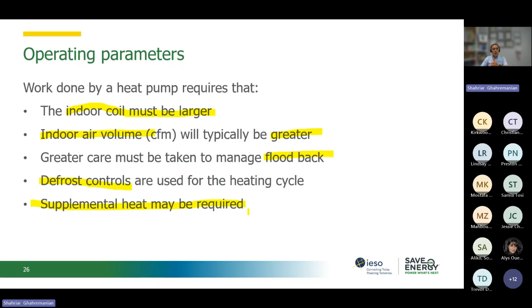And the defrost controls as well, during the heating cycle. Again, this is a control inside. If we see that there is no heating coming into the building but our heat pump is working, that's the time that the system is doing the defrost. And the most important one is that supplemental heat may be required, depending on the climate zone that we are in, the sizing of the heat pump, and its efficiency. Supplemental heat means that when the outdoor temperature becomes lower than a certain temperature, we need to shut down our heat pump system and use the supplemental heat that we have.